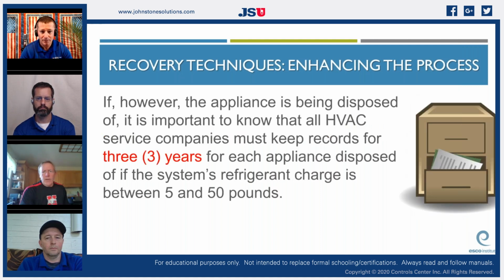It basically just becomes a liquid line receiver. It does. You're just kind of pushing it in. That's exactly right. And again, we're trying to be fair to the homeowner. As R22 especially got so expensive, we were just trying to, well, we'll just recover it in this and not into the 50-pounder, which means we could be exposing them to somebody else's refrigerant, which is actually breaking the EPA regulations. So again, keep your records for 3 years.